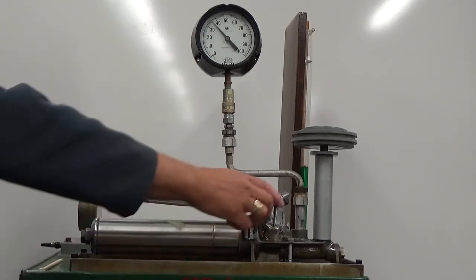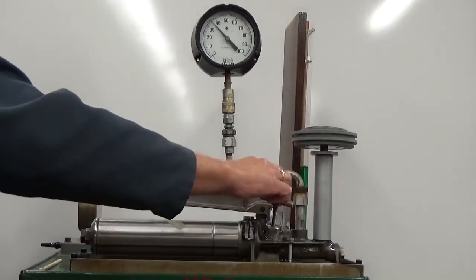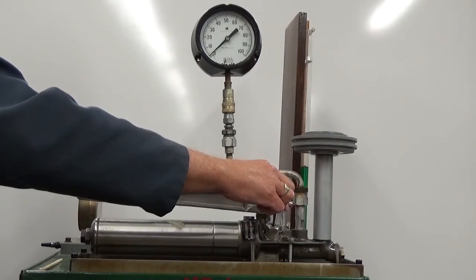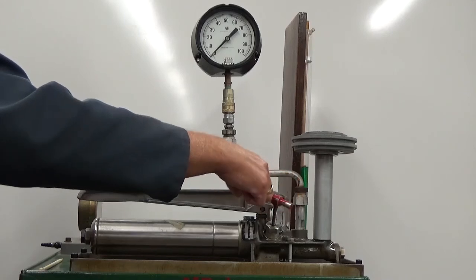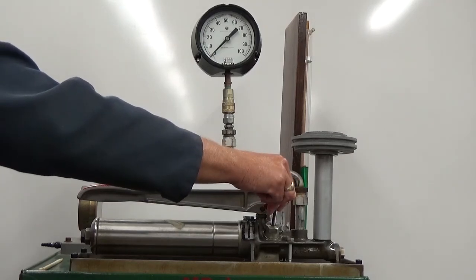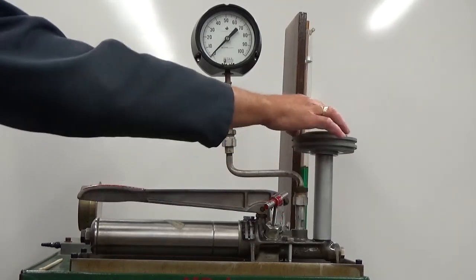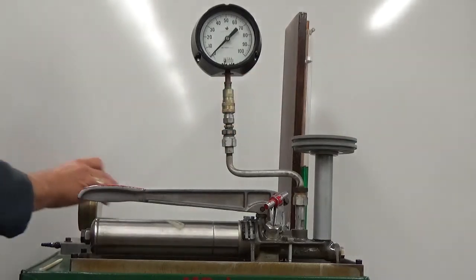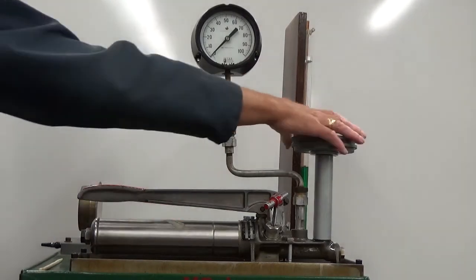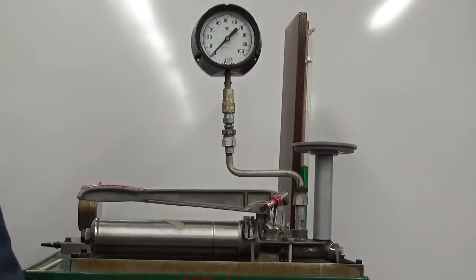To do this, the pressure relief valve is opened to reduce the pressure in the system. Calibration weights can then be removed or added to whatever is required for the next calibration point. The process is then repeated and pressurized, and the next value is then recorded, thereby completing the calibration for the gauge, which can then be used in the field.